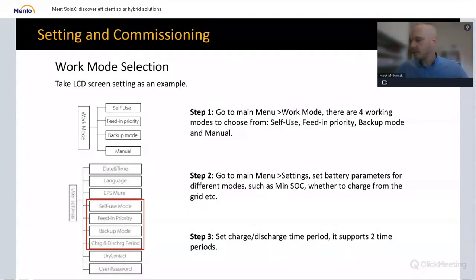You can change your work mode if you don't like to work with self-use. About 90 or 95% of users use the self-use work mode, but you can change that work mode to something else. It can be feed-in priority, backup mode, or manual. Manual is used when you need to force charge or discharge batteries for some reason. If you feel you really need to quickly charge or discharge batteries, you can activate manual and force charge, and it will charge the battery no matter from where, even easily from the grid.